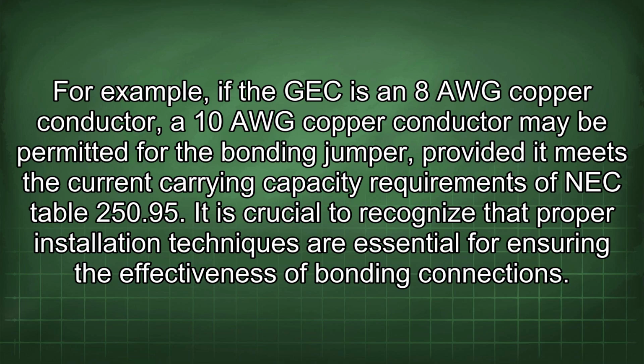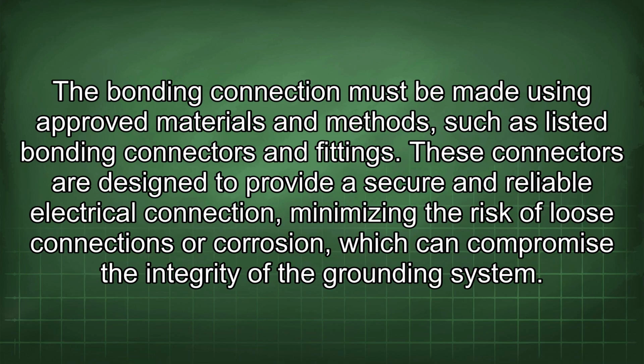It is crucial to recognize that proper installation techniques are essential for ensuring the effectiveness of bonding connections. The bonding connection must be made using approved materials and methods, such as listed bonding connectors and fittings. These connectors are designed to provide a secure and reliable electrical connection, minimizing the risk of loose connections or corrosion, which can compromise the integrity of the grounding system.